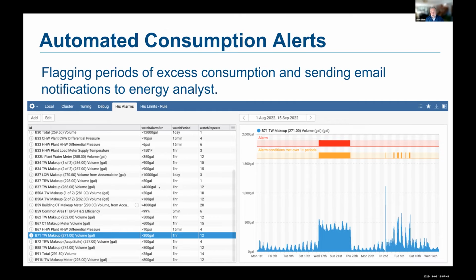We have actually 3 variables that we're setting. So one is a threshold, just like you in an alarm. Has consumption exceeded a certain threshold, but we also define 2 other variables. One is a watch period that we're looking at, and then we set a threshold of the number of occurrences in which the first threshold needs to be exceeded before it will trigger an alarm.